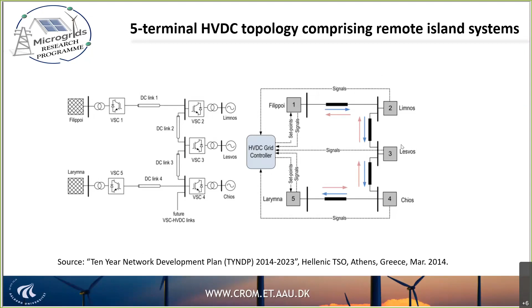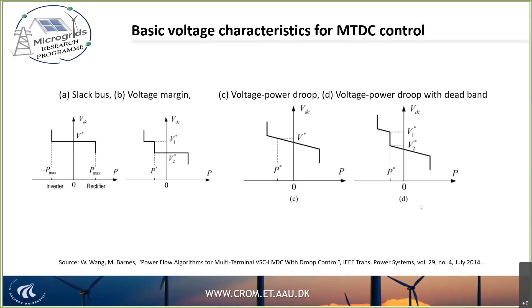In that case, you can see that sometimes we have slack buses, meaning that we fix the voltage, and it doesn't matter how much power there is within some limits. Sometimes we define voltage margins, but when we want power sharing, we define voltage versus power droop functions. We could also have dead bands, for instance so the system can work in constant power mode between some possible voltages, and then it can droop down when we just decrease this voltage, automatically power goes down, and vice versa. So this would be the droop operation mode in that case.